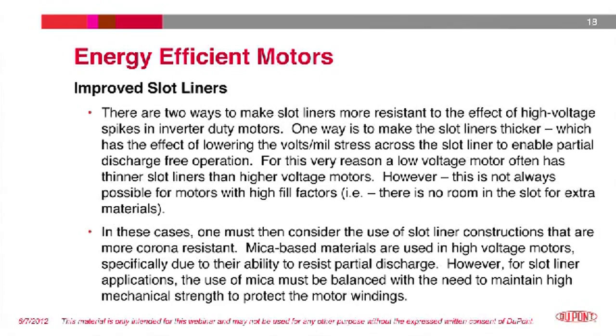For this very reason, a low voltage motor often has thinner slot liners than higher voltage motors. However, this is not always possible for motors with high fill factors. For example, there's no room in the slot for the extra materials. In these cases, we must then consider the use of slot liner constructions that are more corona resistant. Mica-based materials are used in high voltage motors, specifically due to their ability to resist partial discharge. However, for slot liner applications, the use of mica must be balanced with the need to maintain high mechanical strength to protect the motor windings.